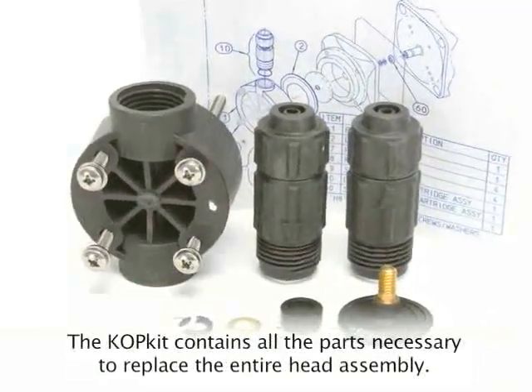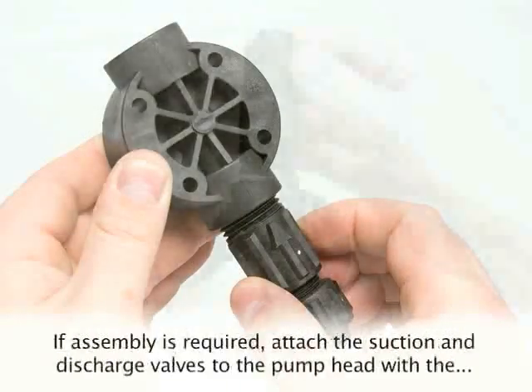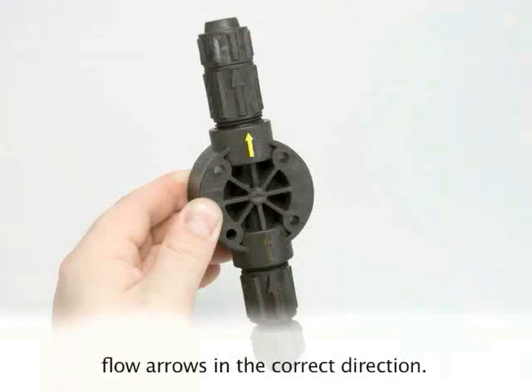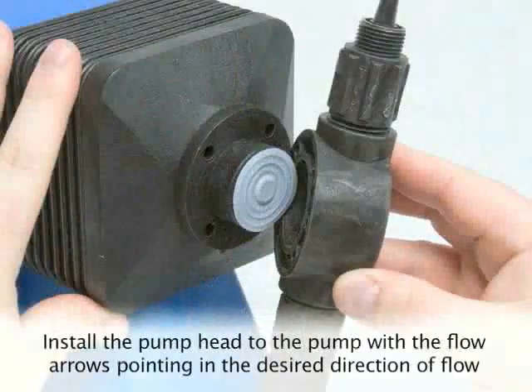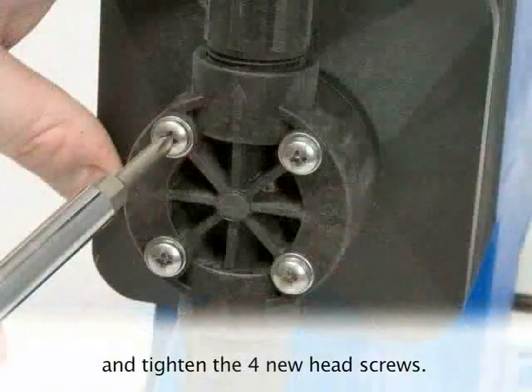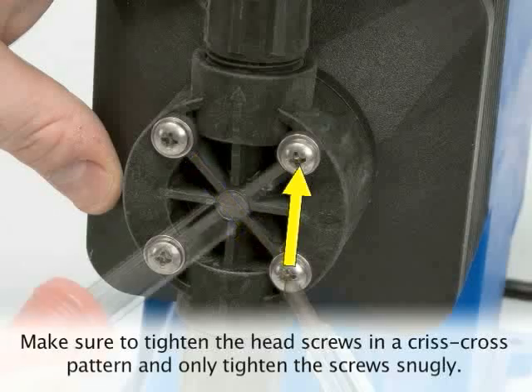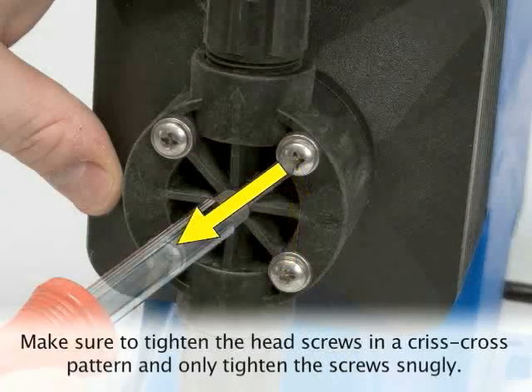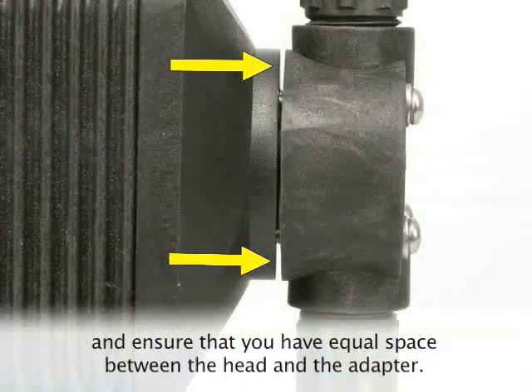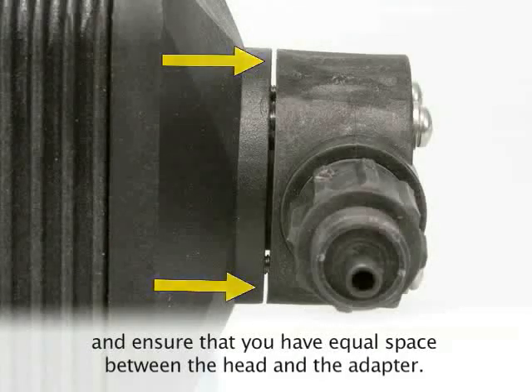The KOPkit contains all the parts necessary to replace the entire head assembly. Depending on your pump's KOPkit, it may or may not come assembled. If assembly is required, attach the suction and discharge valves to the pump head with the flow arrows in the correct direction. Install the pump head to the pump with the flow arrows pointing in the direction of flow and tighten the four new head screws. Make sure to tighten the head screws in a criss-cross pattern and only tighten the screws snugly. Verify that the head is not over-tightened to one side by looking at the space on either side of the head and ensuring that you have equal space between the head and the adapter.